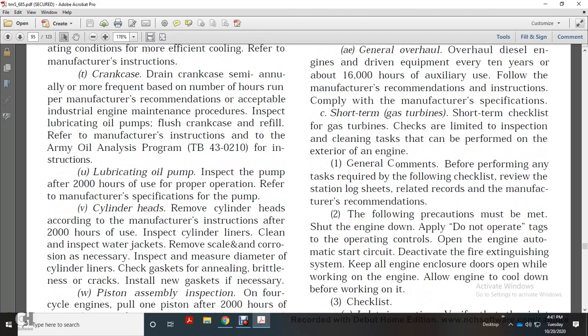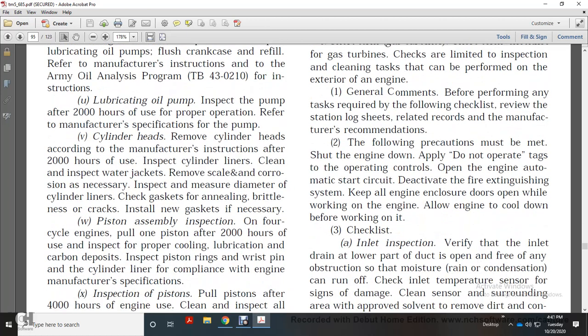Shut the engine down. Apply a Do Not Operate tag to the operating controls. Open the automatic start circuit. Deactivate the fire extinguisher system. Keep all the engine enclosures open while working on the engine. Allow the engine to cool down before working.